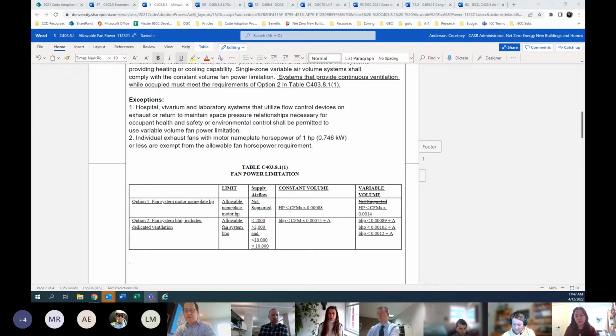So the idea is we want to establish a standard that can be readily met with good design, and projects that can't meet these for some reason would be limited to outliers that maybe have an unusual design layout or scoping. But with good duct design, there should be some means to reduce these limits. Also, a lot of these systems provide ventilation and run continuously, so fan energy can be a large component of the overall HVAC energy use.